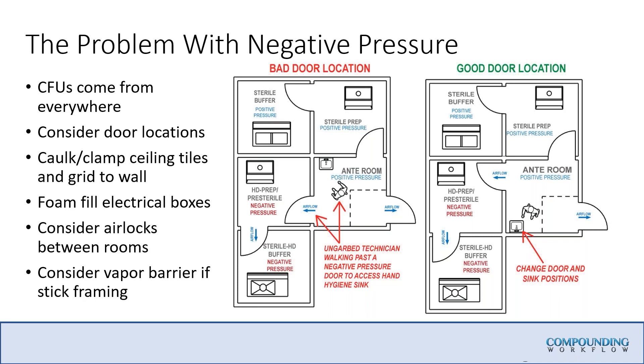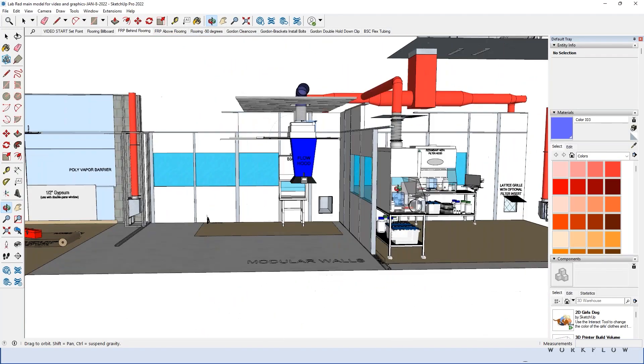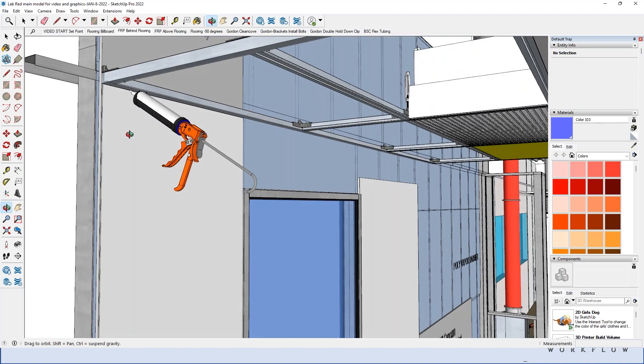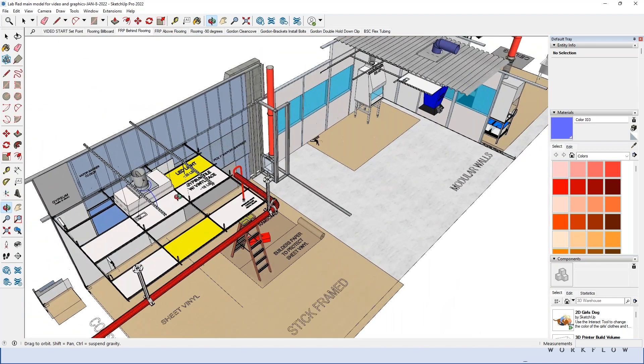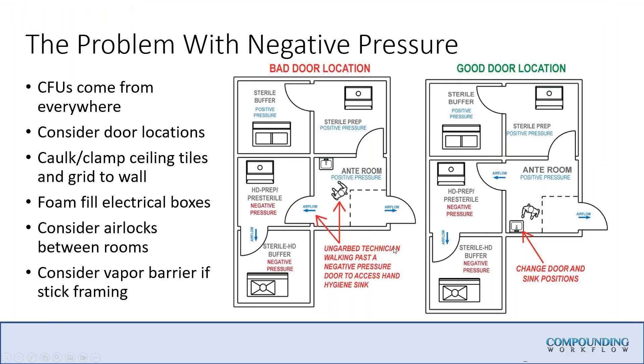There are a couple of states that absolutely want to see the caulking. Let me jump over to the model to show you this as part of the design criteria. Where the ceiling grid meets the wall, you want to make sure there's caulking there — that is a space. We're essentially trying to create a submarine hatch. We want to make sure we're clamping from above to get good natural compression to the ceiling grid so that none of that dirty air gets pulled into the ISO-rated air areas.